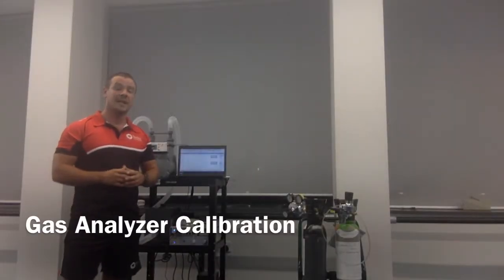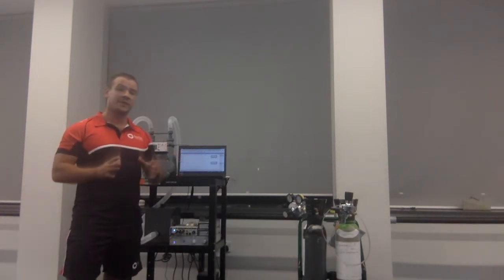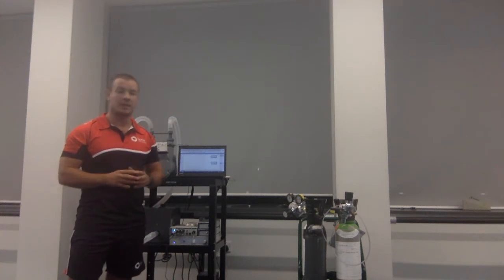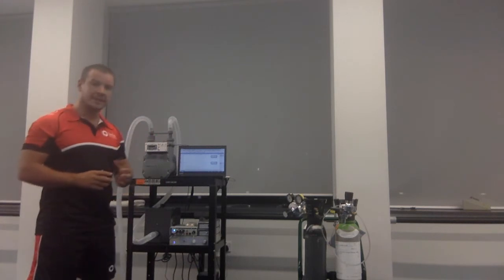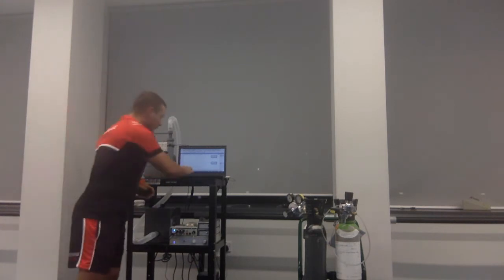To calibrate the gas analysers, I need to run through two samples of air with different but known concentrations of carbon dioxide and oxygen. One of these samples of air will be ambient room air, and we know that oxygen accounts for about 20.93% and that carbon dioxide accounts for about 0.04%. I then have a cylinder of gas, and the concentrations of oxygen and carbon dioxide in there are 16 and 4% respectively.